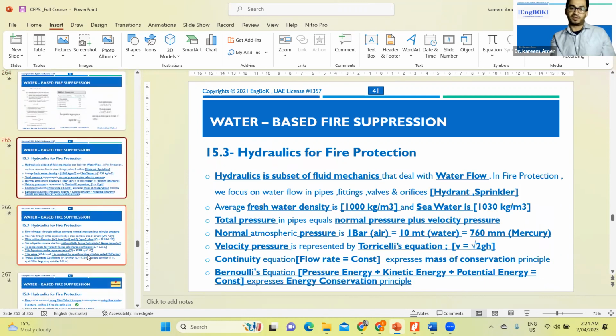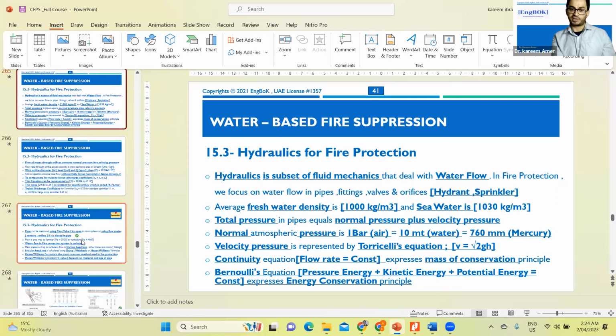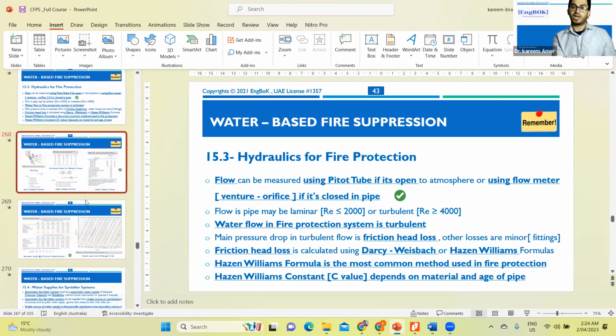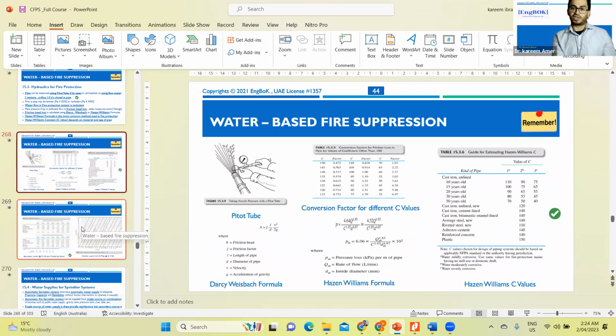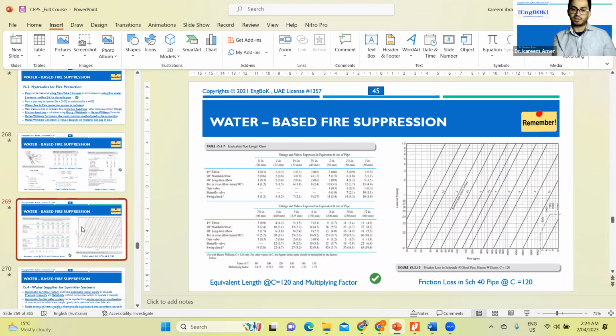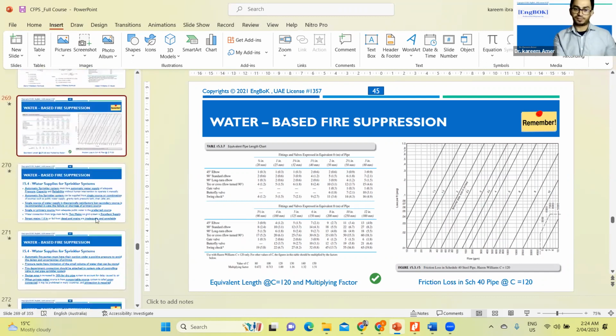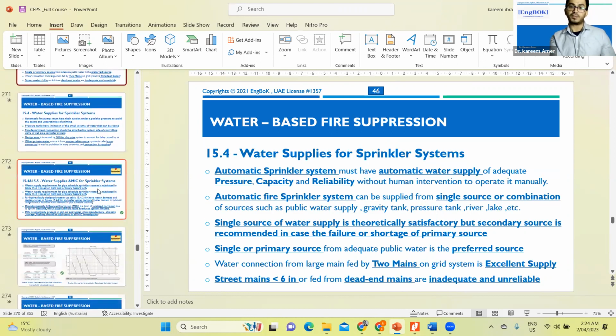Also, we have here a very important part for engineers, hydraulics for fire protection. We discussed the Bernoulli equation, Hazen-Williams equation, Darcy equations, equivalent lengths, measurement of flow by pitot tube, like by Venturi, and whether it's an open system or closed system. What is the C factor, how do you calculate it? What is the standard C factor, 120 or 100, 130, 150, and how do we make interpolation in order to calculate the friction loss, the equivalent length?